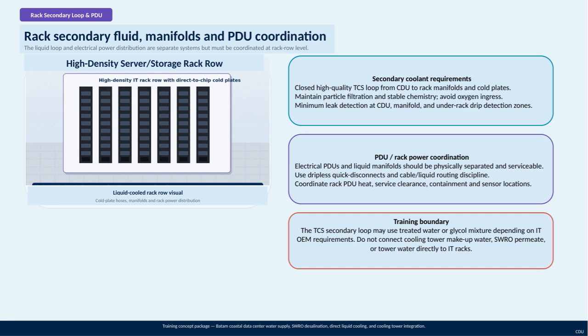The secondary coolant loop is a closed, high-quality system that runs from the cooling distribution unit, or CDU, to the rack manifolds and cold plates. This loop must maintain strict particle filtration and stable chemical balance to prevent contamination, and it's essential to avoid oxygen ingress, which can degrade the system over time. Leak detection is another key requirement, with sensors placed at the CDU, manifold, and under the rack in strategic drip detection zones to catch any issues early.